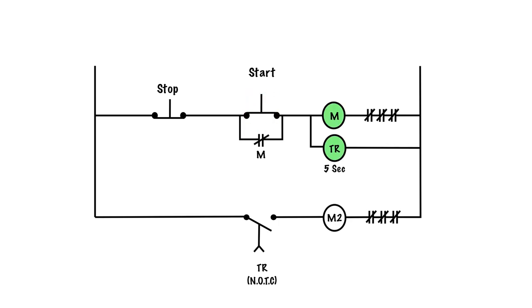I go ahead and press the start button, which will energize M coil, which will close M contacts, which will also energize the time relay here because it is in parallel with the coil. When I let my finger off the start button, these two will stay energized due to the hold-in, seal-in, or auxiliary contact that provides a parallel path around this open switch.